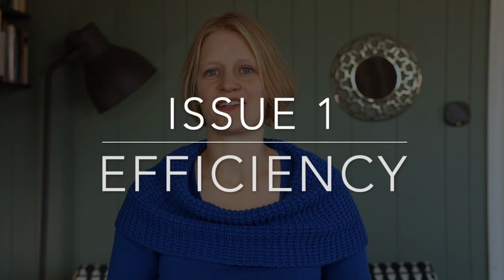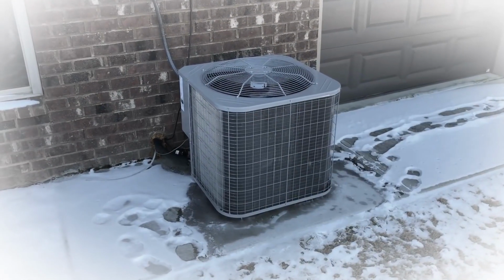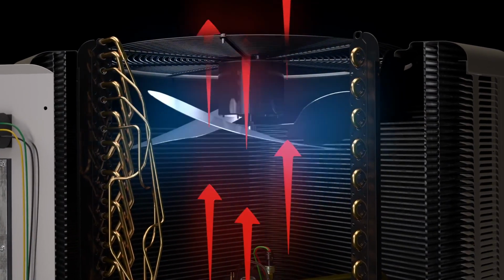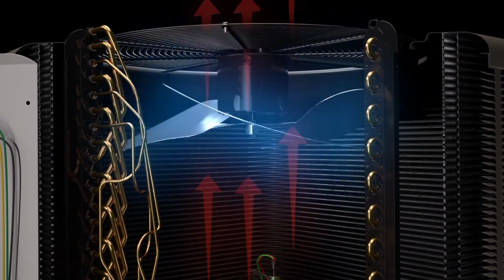The misconception is often that bigger is better, but when it comes to heat pumps, that's not the case. The efficiency of a heat pump is at its peak when it's running consistently at its intended capacity. Oversized heat pumps often experience short cycling, meaning they turn on and off frequently. This constant cycling not only reduces the overall efficiency of the system, but also puts unnecessary strain on the components.